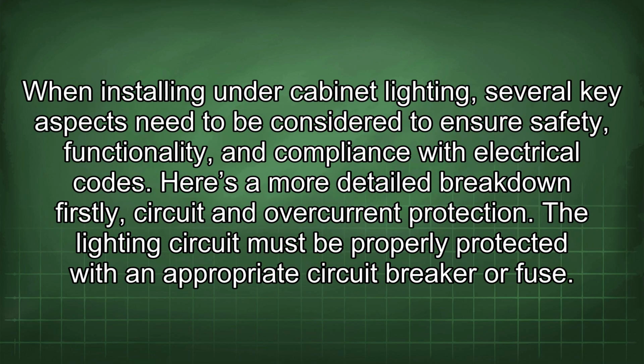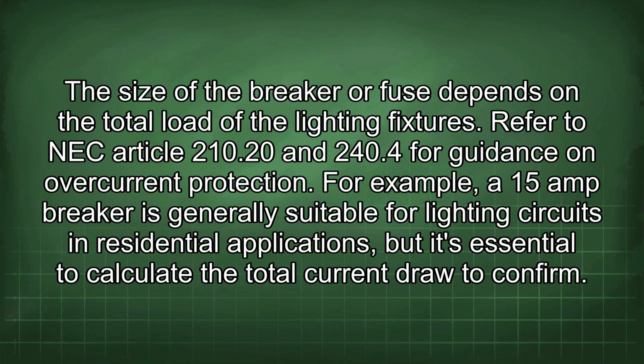When installing under-cabinet lighting, several key aspects need to be considered to ensure safety, functionality, and compliance with the electrical codes. Here's a more detailed breakdown. Firstly, circuit and overcurrent protection. The lighting circuit must be properly protected with an appropriate circuit breaker or fuse. The size of the breaker or fuse depends on the total load of the lighting fixtures. Refer to NEC Article 210.20 and 240.4 for guidance on overcurrent protection. For example, a 15 amp breaker is generally suitable for lighting circuits in residential applications, but it's essential to calculate the total current draw to confirm.